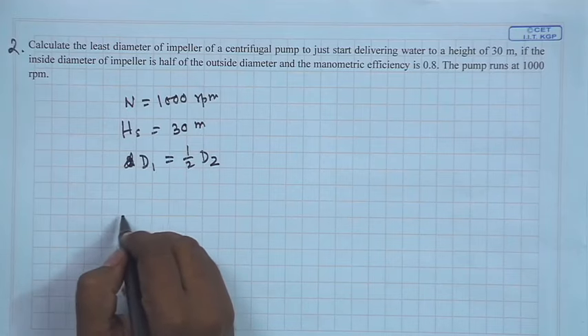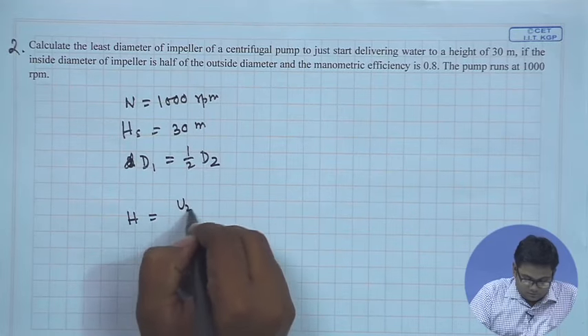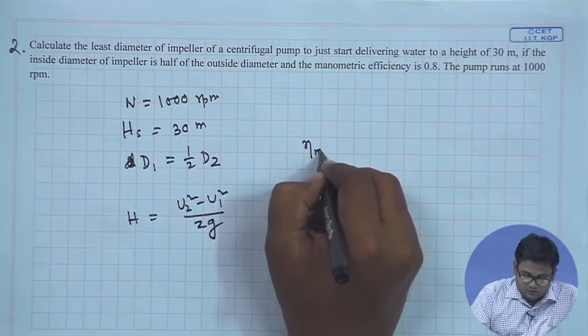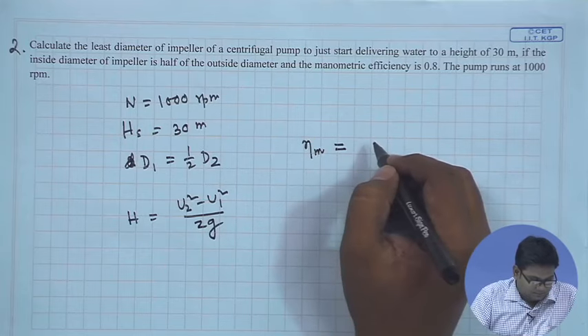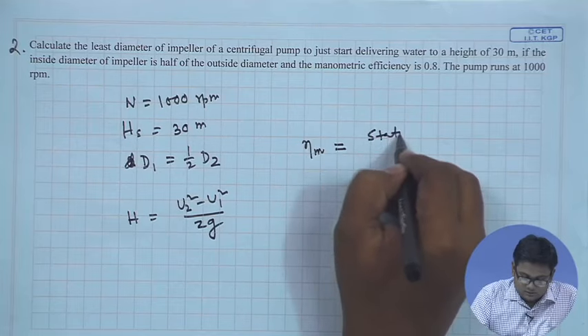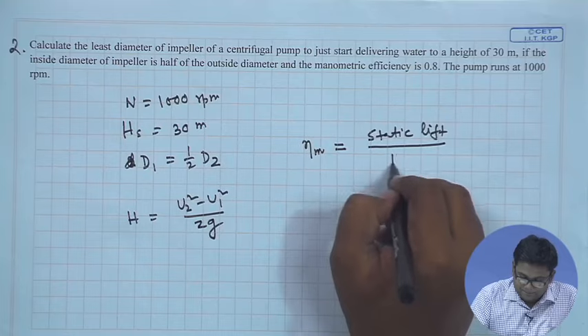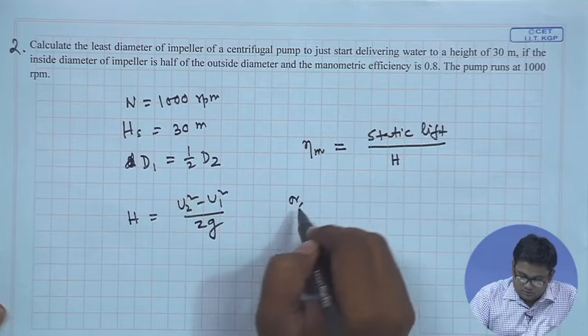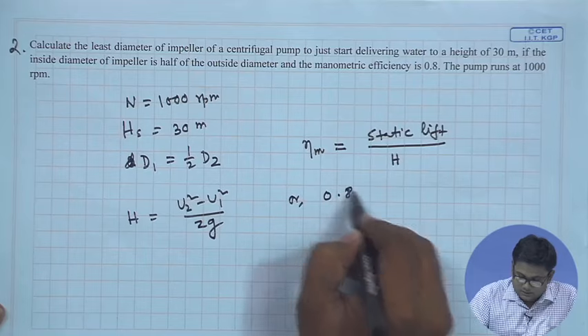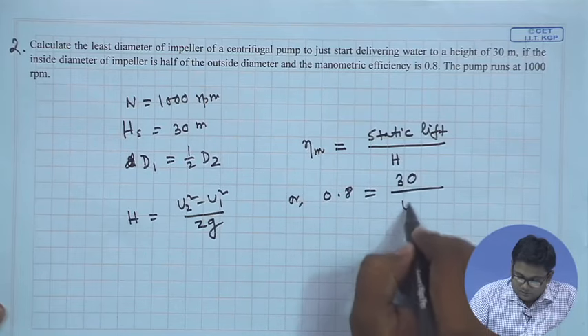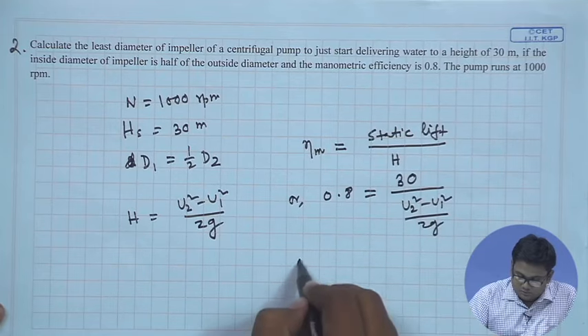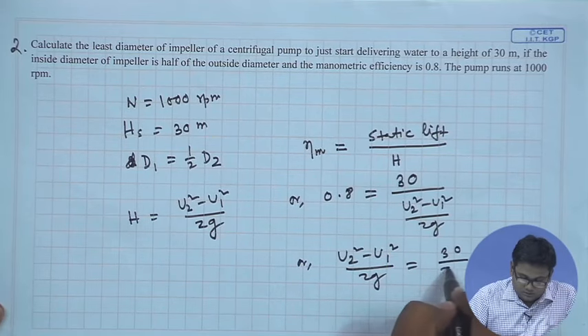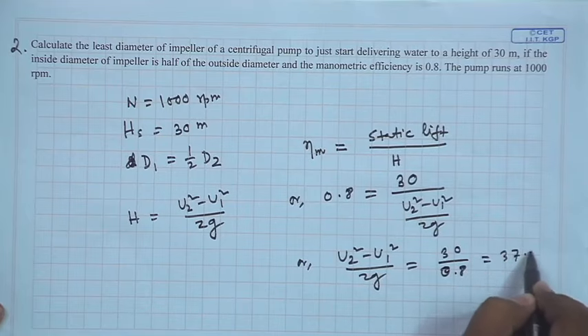When the pump is just starting, the head developed is the centrifugal head: H = (u2² - u1²) / 2g. The manometric efficiency is given by the static lift over the centrifugal head: η_m = static lift / [(u2² - u1²)/2g]. With η_m = 0.8 and static lift = 30 m, we get (u2² - u1²)/2g = 30/0.8 = 37.5 m.